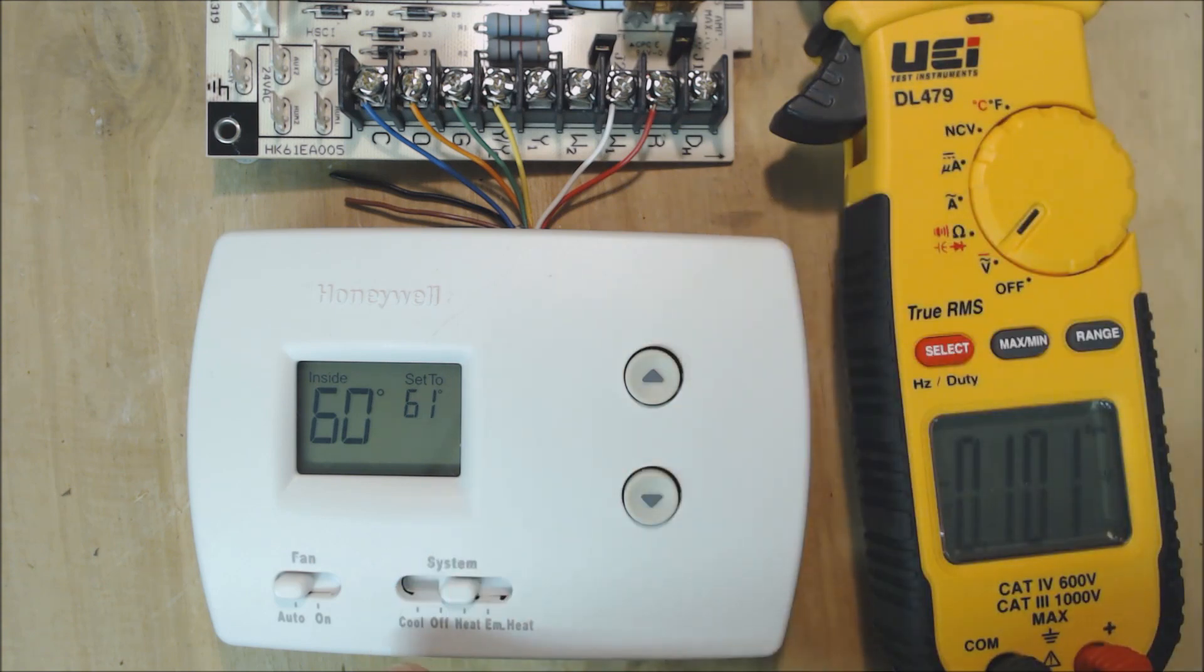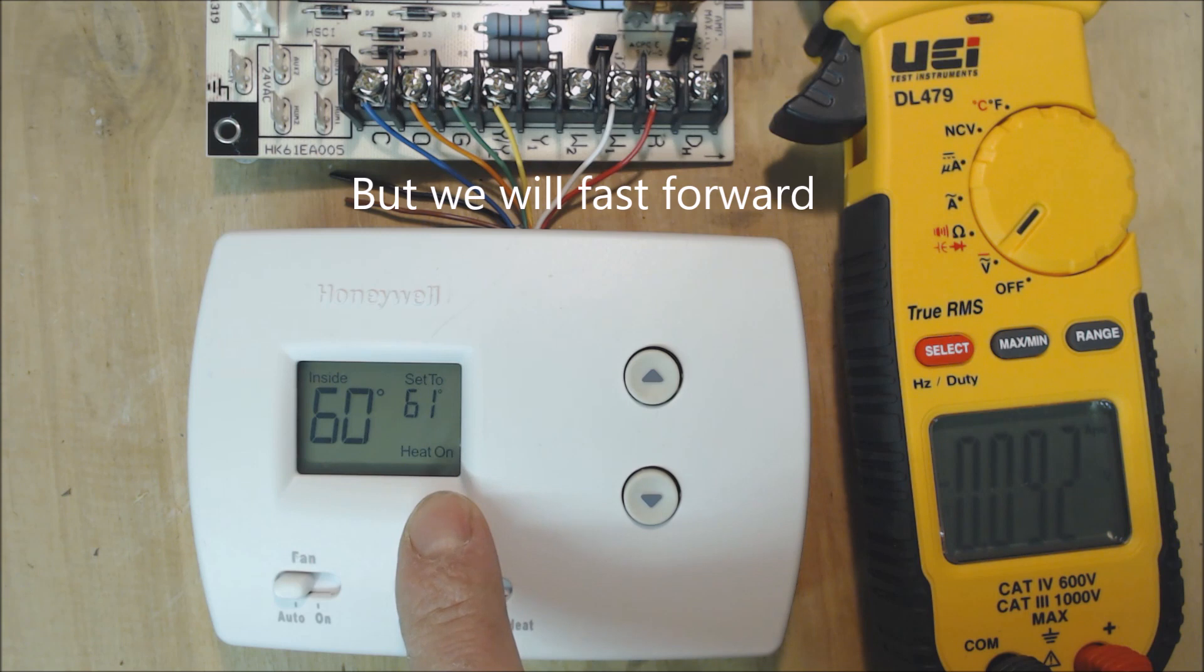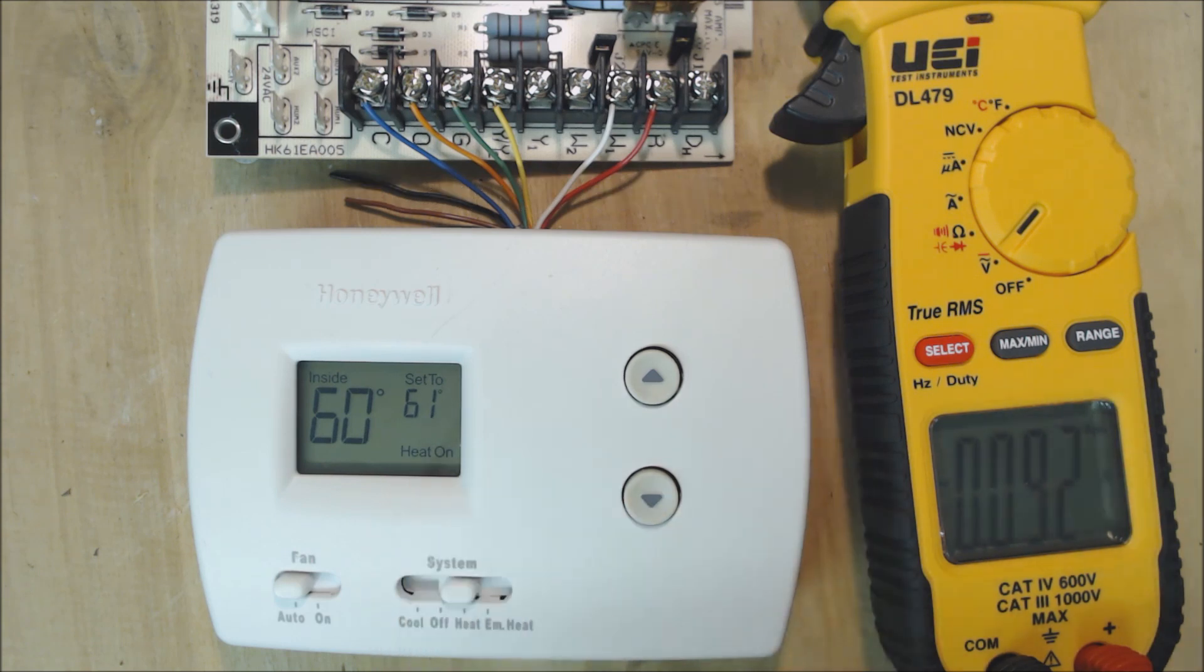That five minutes is crucial for compressor safety. If you just tried to turn it from cooling straight into heat and the compressor shut off, the compressor is going to have a hard time trying to turn back on again, and that's going to end up hurting the compressor. That's why we're waiting for this five-minute delay with this heat on flashing.